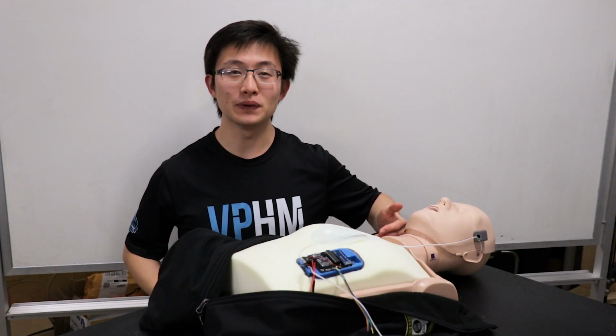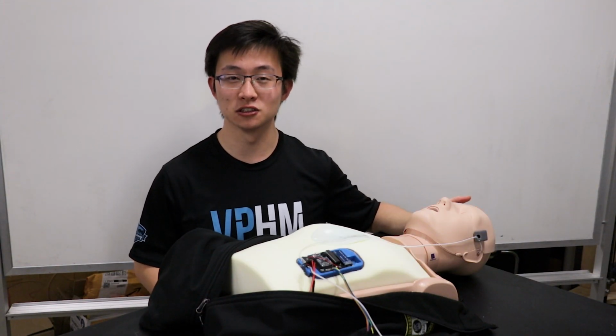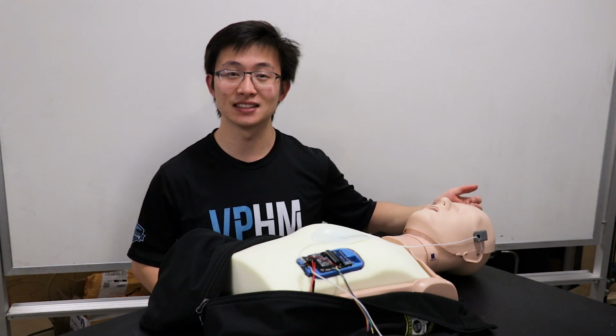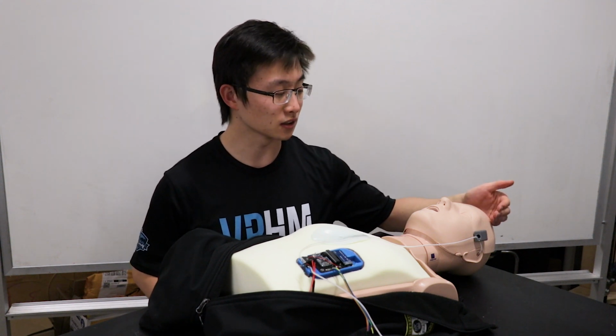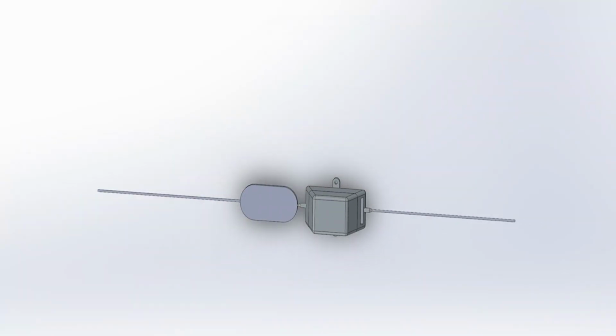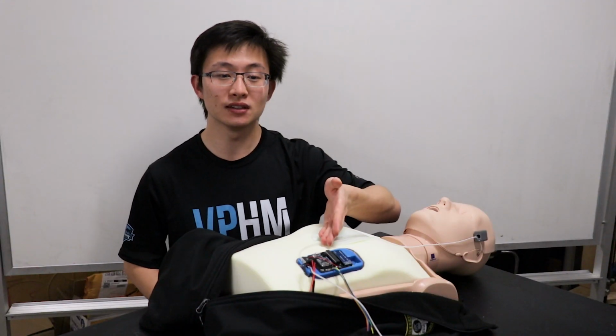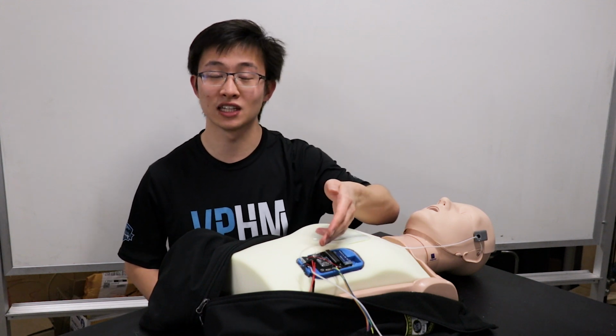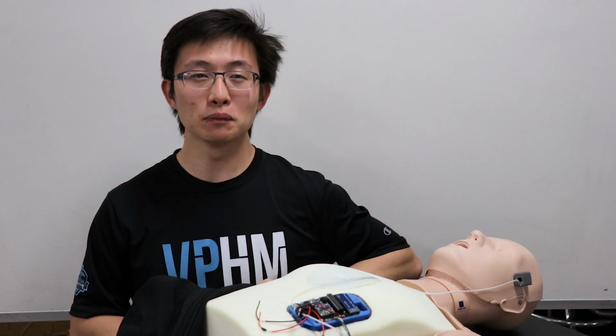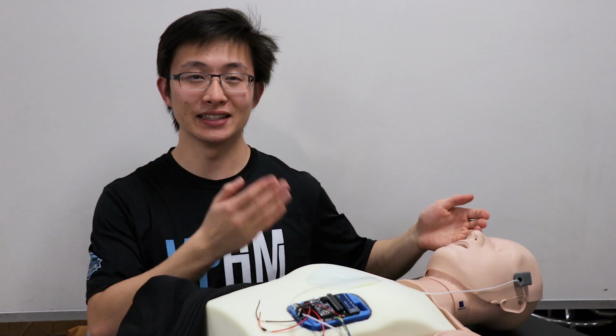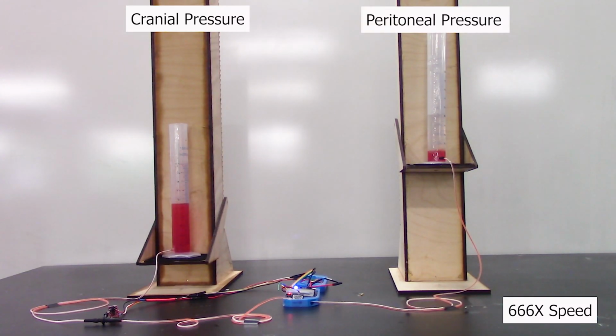The CephloPump would be implanted during routine shunt surgery, acting as an add-on to any existing shunt system. Near the skull, the surgeon will connect a pressure sensor, which will go in front of the shunt valve. In the abdomen, the surgeon will connect the tubing to the CephloPump. The CephloPump reads the pressure in the head and in the abdomen. From this information, it decides whether to turn on the micropump to assist in pulling fluid from the skull.